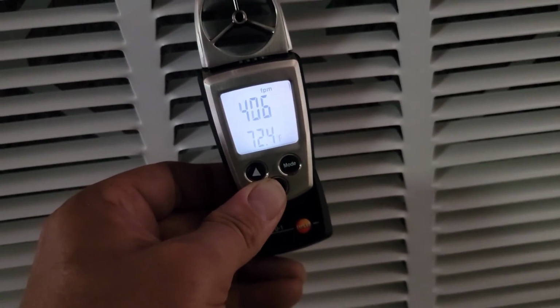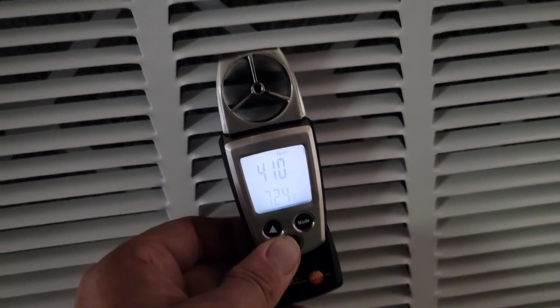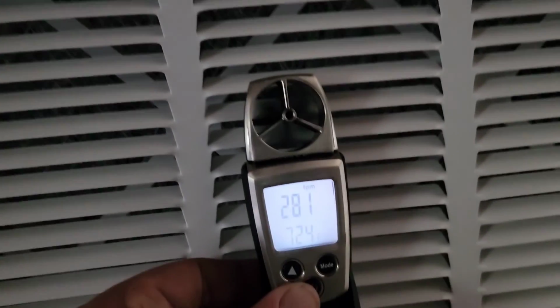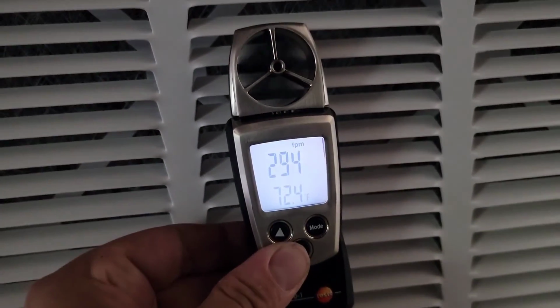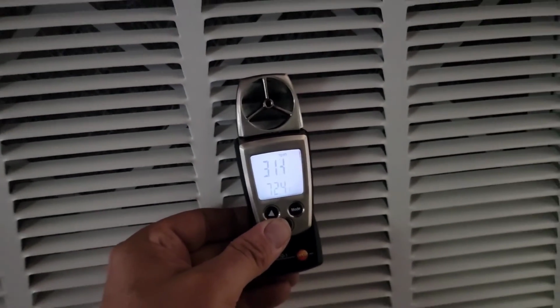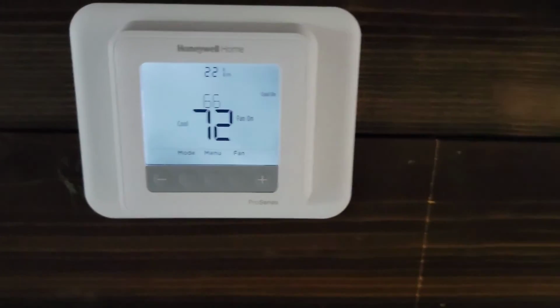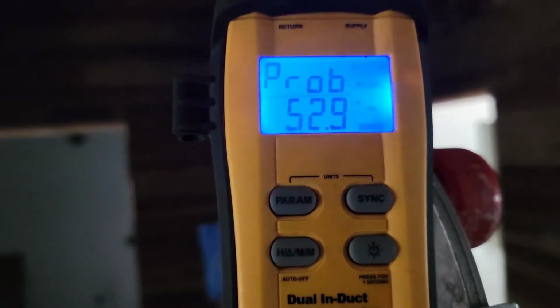450 at the bottom of the return grill. In the middle, 400 up top, about 290. So nothing over 500. That's great. Excellent. 72 degrees in the house. Unit's been running about 10 minutes. Taking a reading with the dual in-duct psychrometer. It's 52 degrees in the supply vent. So 20 degree split. Love it.